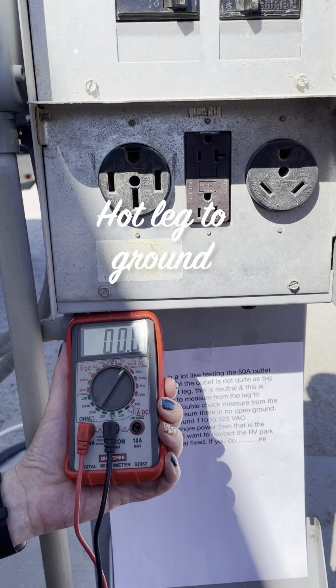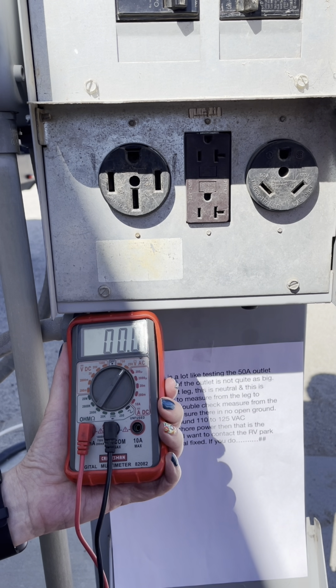Next, we'll test the 30 amp outlet. We will not need the screwdrivers for that because my meter will reach. So this is ground, this is hot, this is neutral. So we're going to measure from neutral to hot. Should get around 120 volts. And then we want to measure from hot to ground. This proves we don't have an open ground, and I have 120 volts. If any of these test poorly or not correctly or less than 120 volts, then you'll need to contact the RV park and have the pedestal fixed.